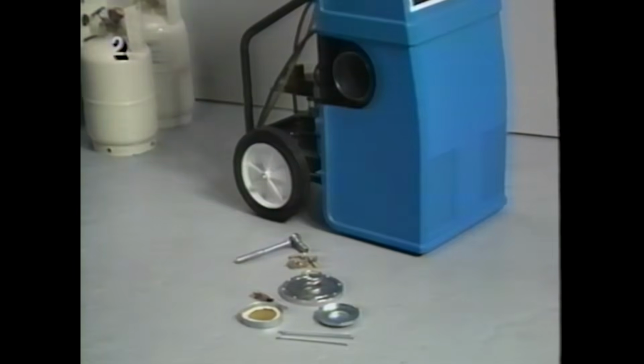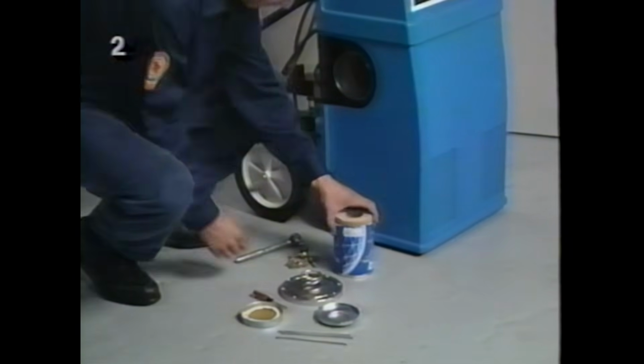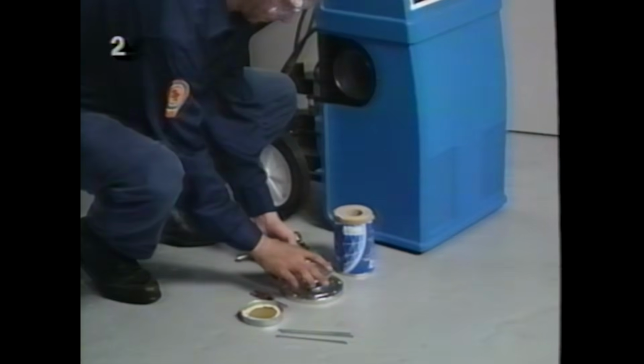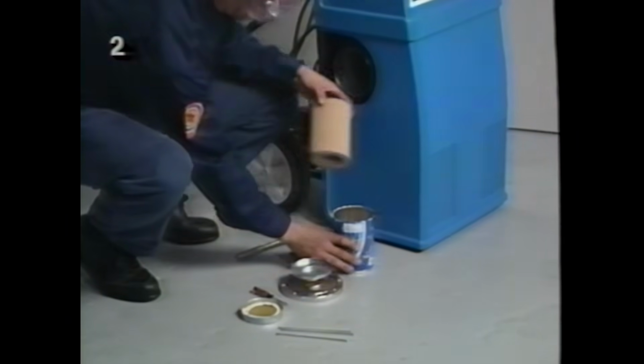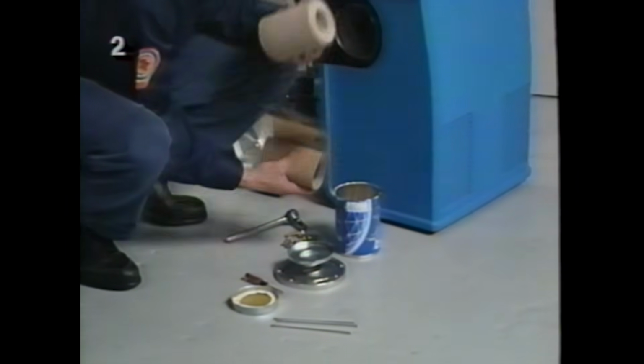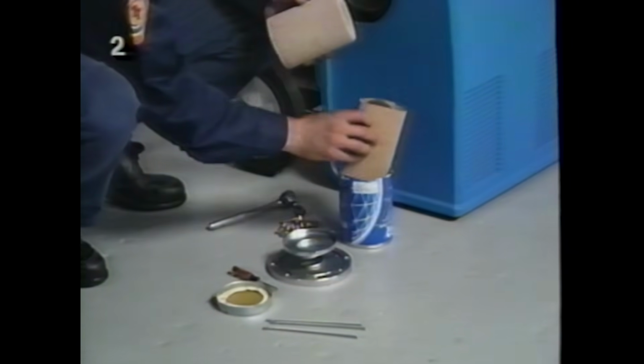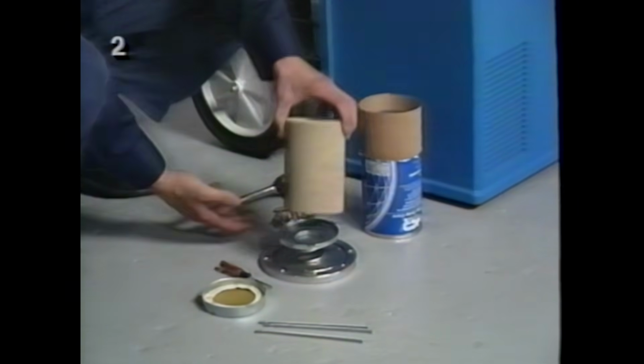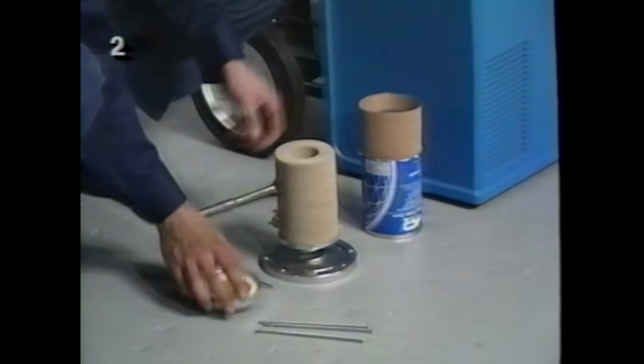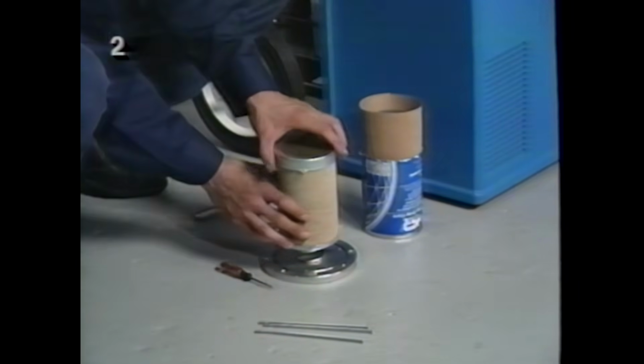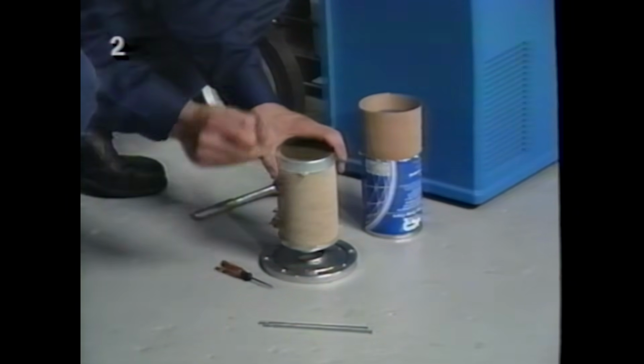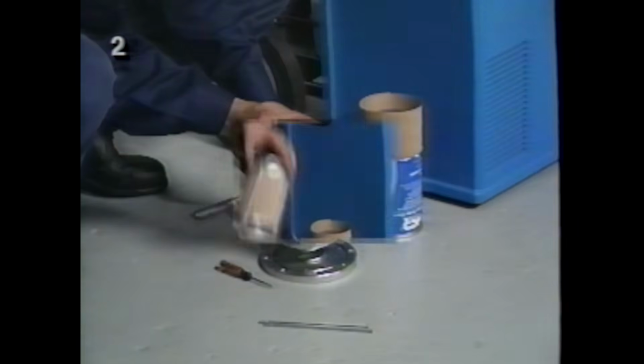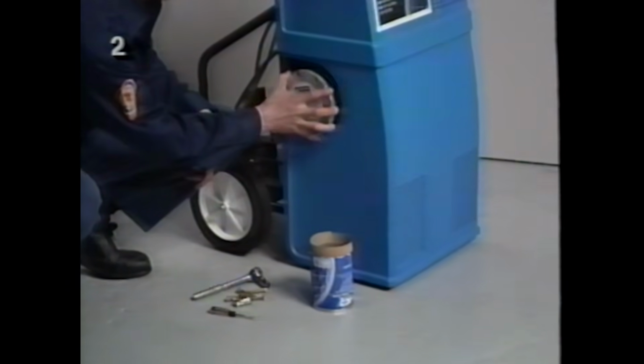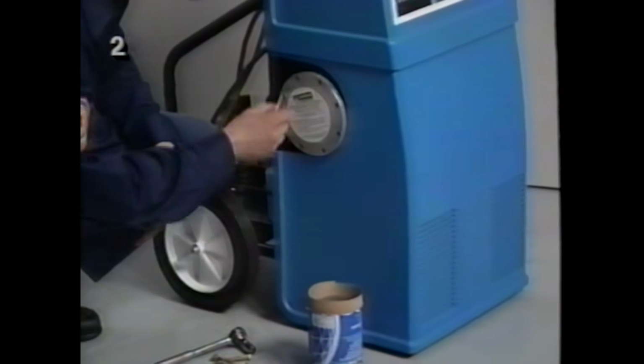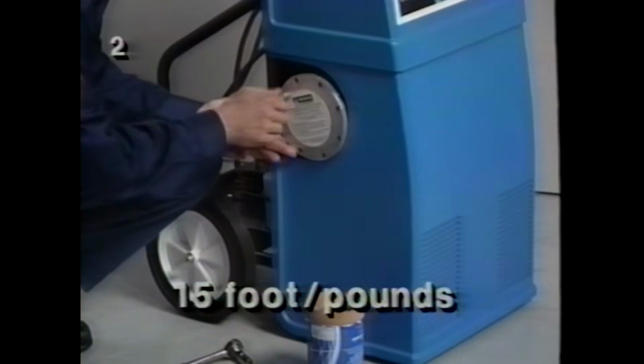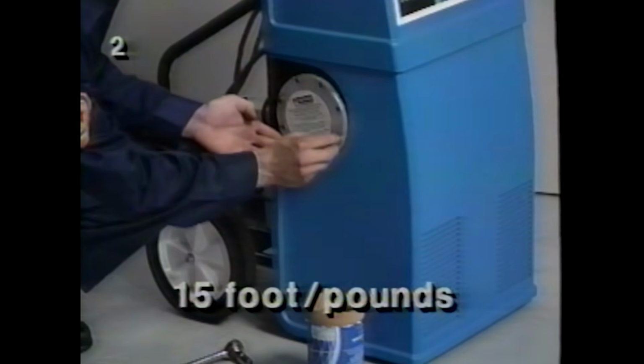The spring goes in the center of the filter cap. The upper bracket goes onto the spring and the center boss fits into the coil with the plate edges facing upward. Then the filter dryer core goes on the upper bracket. The screened lower bracket goes onto the core next, and then the tie rods go in. Tighten them all the way. Put the whole assembly into the shell. Put the bolts back in and tighten them down to 15 foot-pounds in a star-shaped pattern.